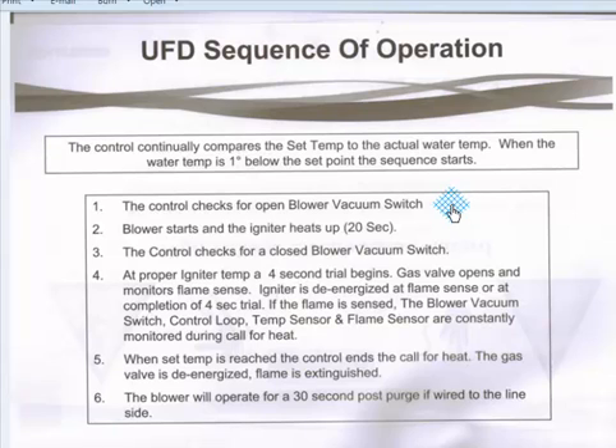First thing it's going to do is start going for safety, and a vacuum switch is a safety. It wants to see an open vacuum switch. The reason why is the blower's not on, and the blower only closes the vacuum switch. So if it sees a closed vacuum switch, it's not going to do anything, just going to give you another error code. Just because, haha, we fooled you.